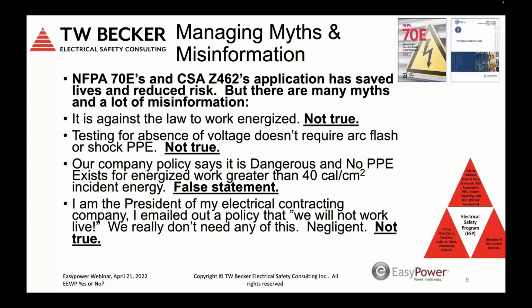I said earlier, it is against the law to work energized. That is not true. But you can interpret regulations depending on the employer that maybe it is. Well, it's not, right? And that's, again, my interpretation, but it's not against the law. And we need qualified persons to be confident that they can perform energized electrical work without retribution, that they're going to lose their qualification ticket as a journeyperson electrician because they're working energized. So there's a problem here too with a lot of these myths, that the worker may refuse to work energized because they believe they're going to lose their ticket. So it's not true. That qualified person, depending on the trade training underneath that designation, is the worker that we do need to perform energized work, and we need them to be confident about it. That's an element of risk.